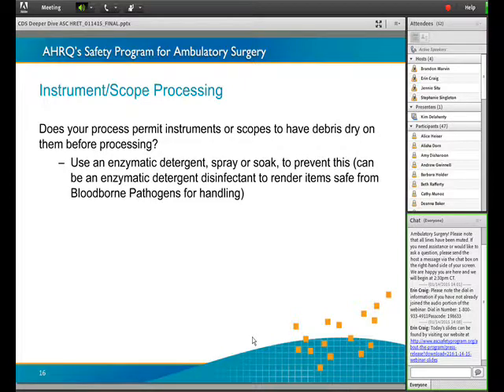So use of an enzymatic detergent, spray or soak, to prevent this is what we recommend. There's now a really cool foam you can use if you're not able to get to the piece of equipment right away for full decontamination and high-level disinfection. You spray it, and it stays moist, with the enzymatic cleaner breaking down that proteinaceous material. It has to be an enzymatic detergent disinfectant to render items safe from bloodborne pathogens for handling - that's the purpose for doing that.